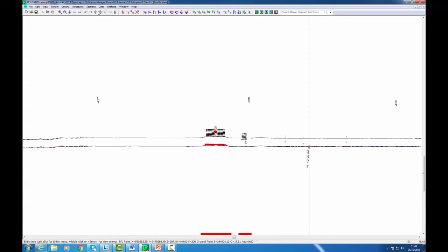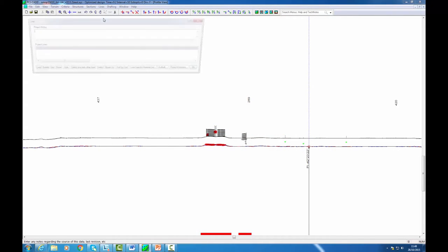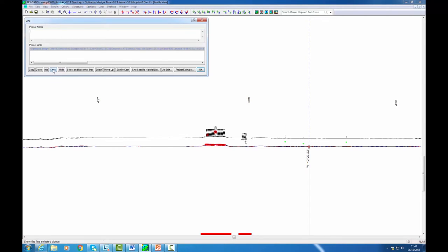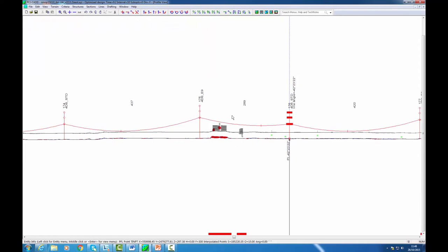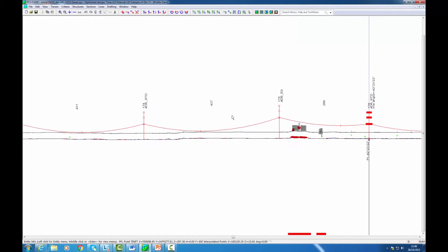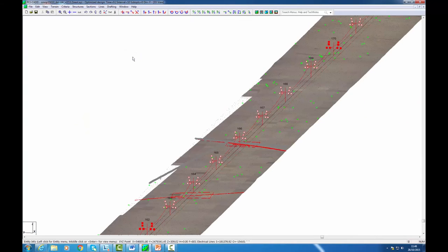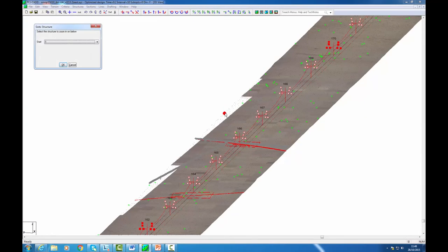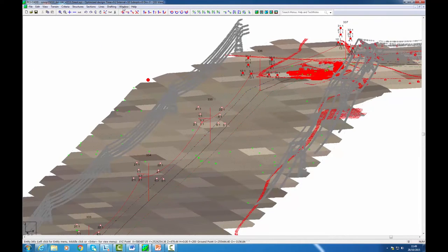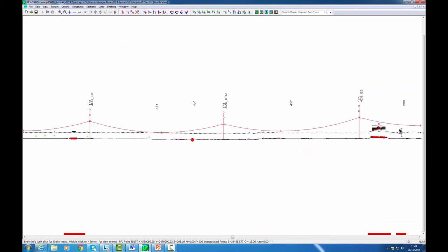What I'm going to do now is to bring the line in. This is the line design, the optimization for this route. And we can see that the line is profiled to meet all of the clearance requirements throughout the route. And we can go to individual structures and check the clearance at that location. So we can see that the clearance requirements are respected.